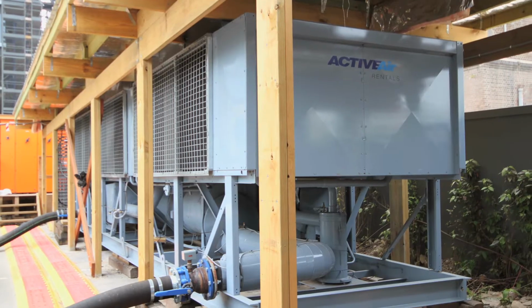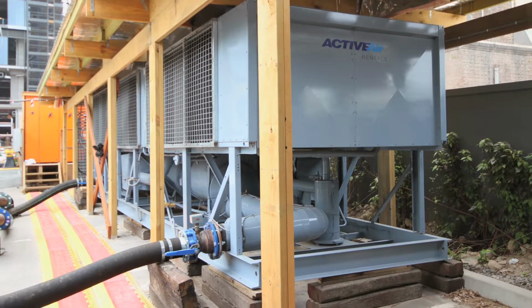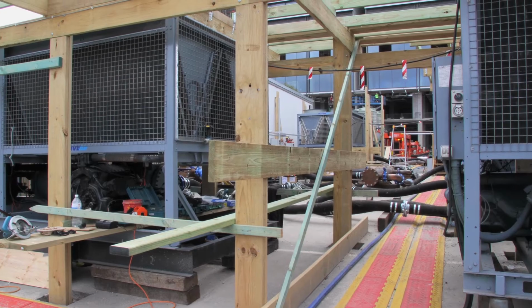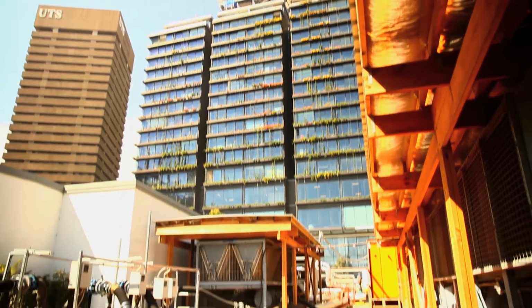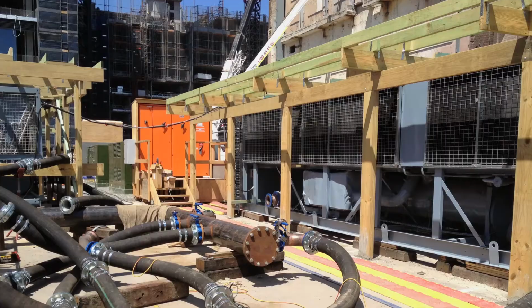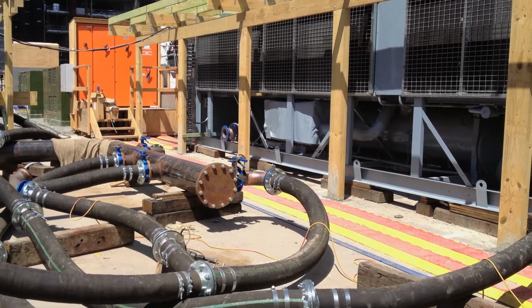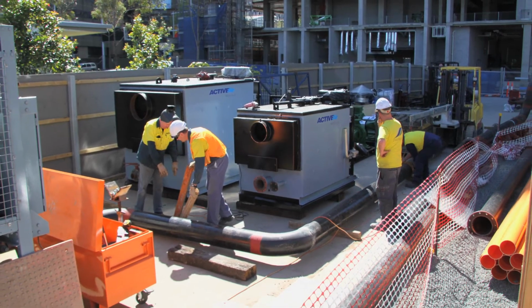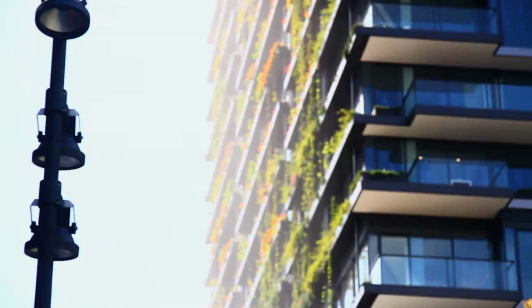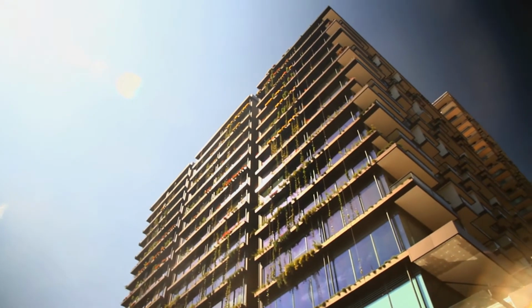We've got an in-house engineering team able to design the structure you see around us, size the correct amount of equipment, the flow rates for the pumps and chilled water, as well as an installation team able to run all the pipework and do everything else required to get it operational. There's a hot and cold water loop around this site that provides all these owners with their air conditioning hot and cold, as well as domestic hot water, and that'll stay there until about November, when our permanent central thermal plant will take over.